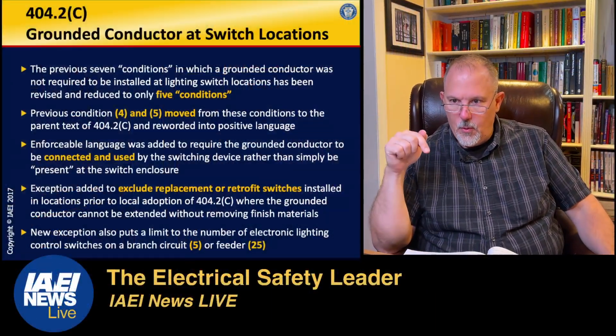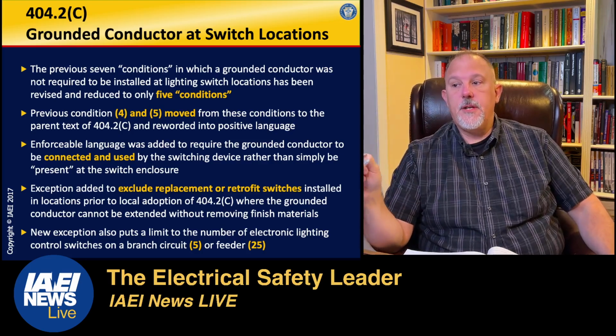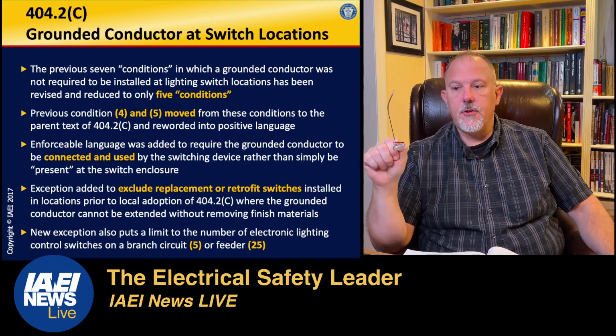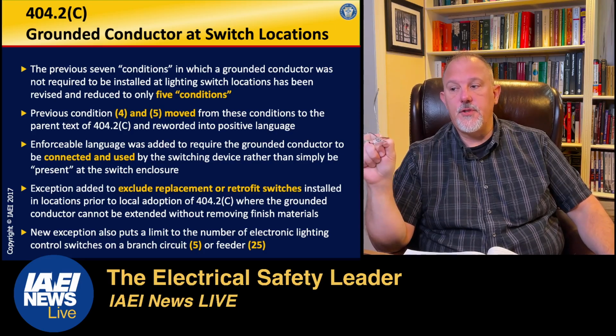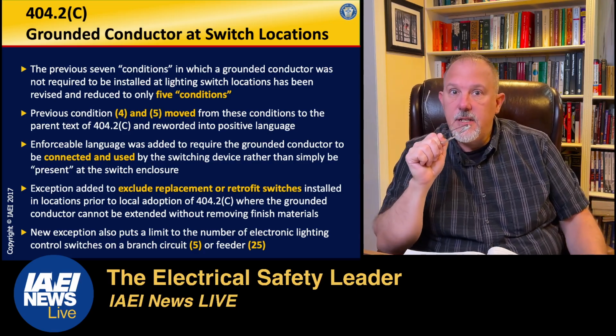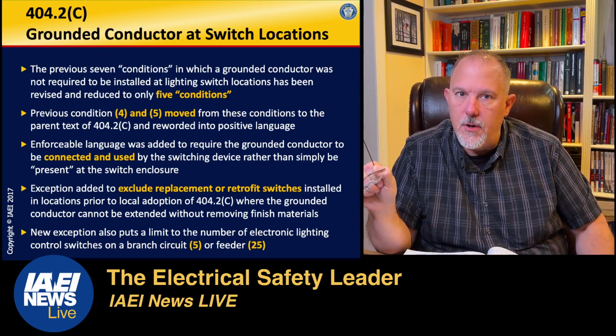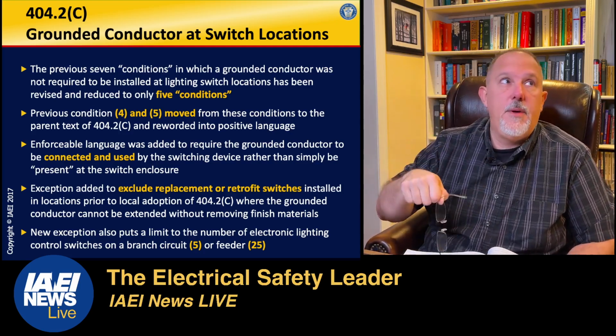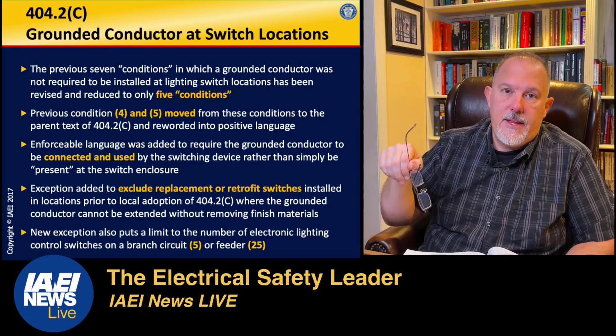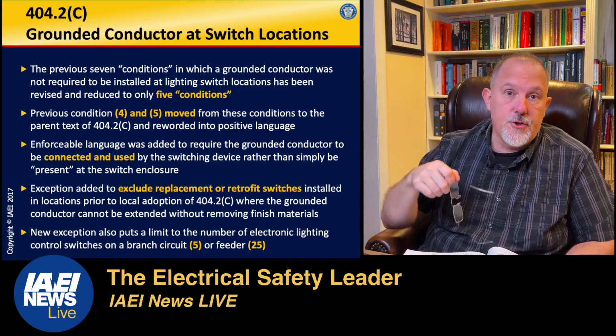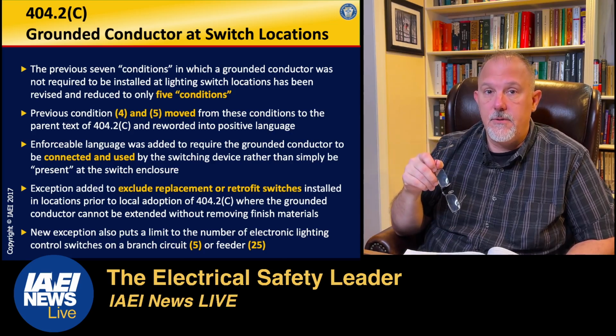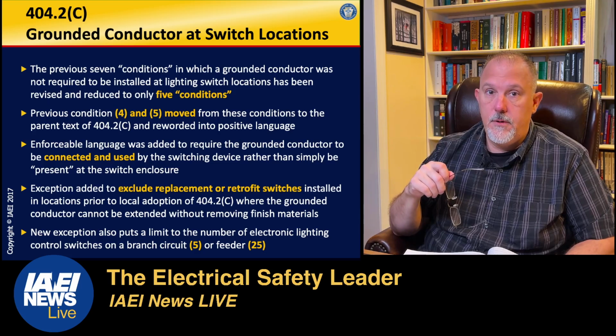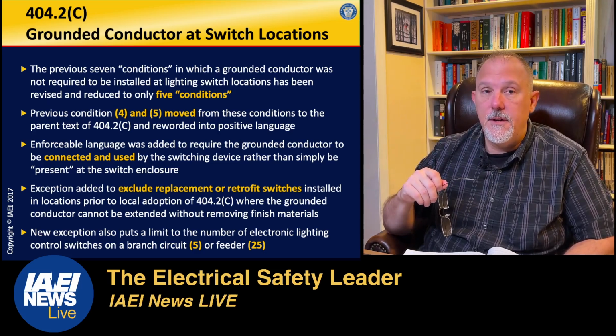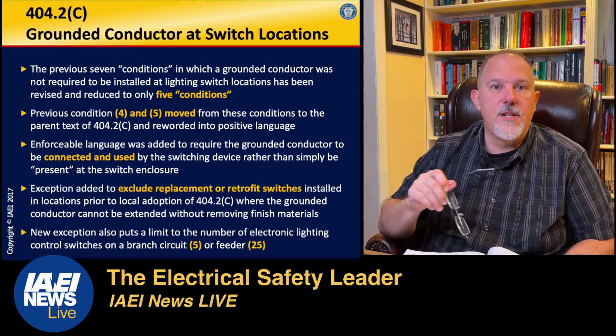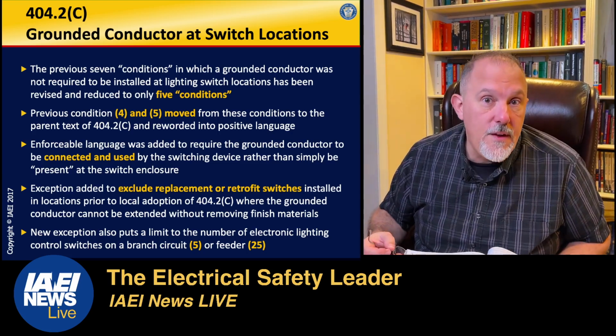Bullet number 1, 2, 3, 4. Exception was added to exclude replacement or retrofit switches installed in locations prior to local adoption of 404.2c, where the grounded conductor cannot be extended without removing finished materials. So they still wanted you to go back and pull that neutral if it was possible. In this basement, if my basement had that case, because I couldn't get a neutral to it, I could see an inspector requiring me to pull that neutral because I have the access and the ability to do it in this basement. If I didn't already do it, which I already did, because I know about Article 250.